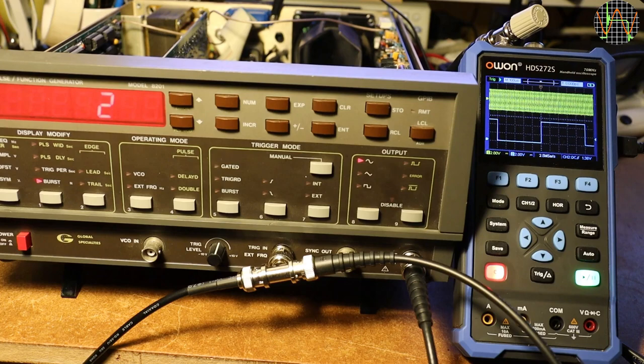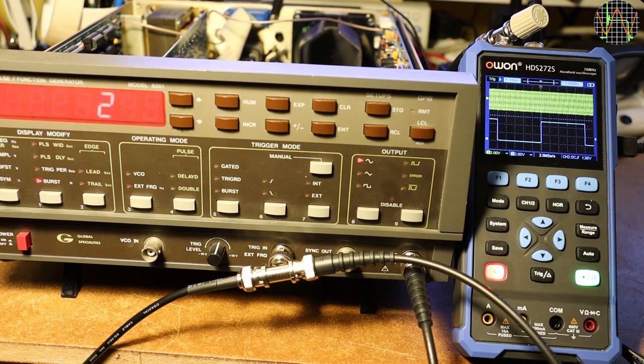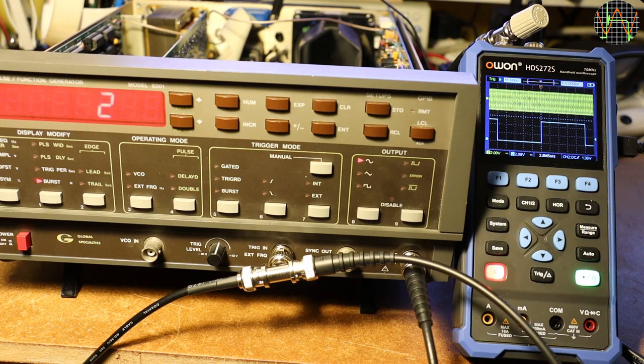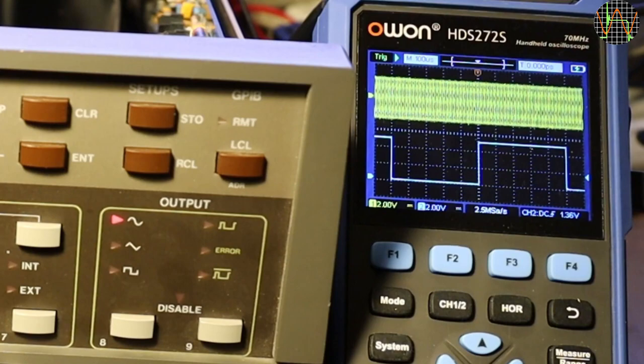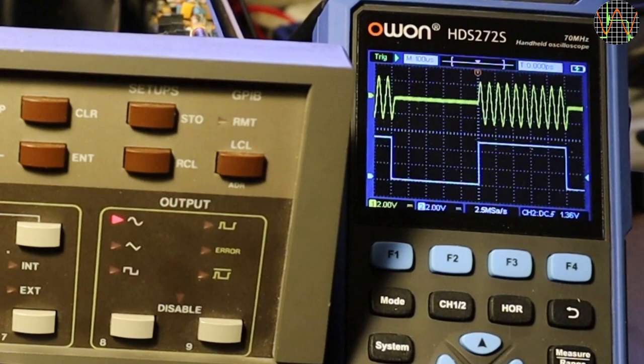To demonstrate the complex gated, triggered and burst functions I set the 8201 to produce a 20kHz sine wave and my other function generator to produce a 1kHz rectangular wave into the trigger input. You can see both the 8201's output and the trigger input on the scope meter which is set to trigger on the external 1kHz signal. Therefore the 20kHz signal is just a blur. If I enable gated, the output will only be enabled as long as the trigger signal is high. So in this case for 500 microseconds which is enough to let 10 periods of the 20kHz signal slip through the gate.